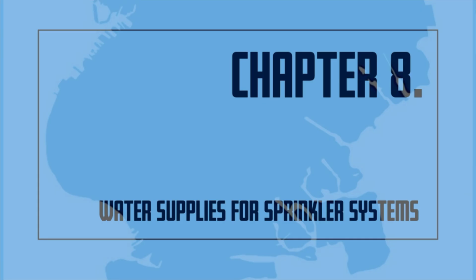Whether a second source is needed depends on several factors. These factors include the strength and reliability of the primary supply, the value of the property, the height, area, occupancy classification, and design of the building. When a sprinkler system is supplied from a public water main, the entire system shall be shut down by closing an indicating type control valve.